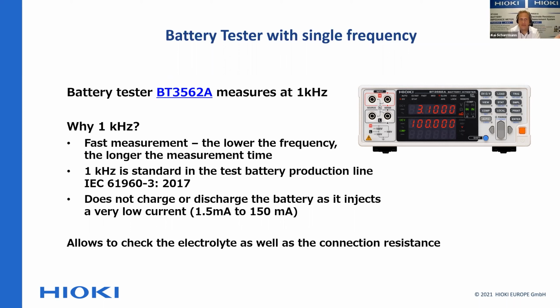But basically it's the BT3562 as far as measurement principle goes. 1 kilohertz is the important frequency. Why 1 kilohertz? It's a fast measurement - the lower the frequency, the longer the measurement time, and at this frequency it doesn't charge or discharge the battery. Also, very importantly, 1 kilohertz is the standard in battery test production lines. There's an IEC standard for that, so you're basically required to do a 1 kilohertz test of your battery before you finish it off.